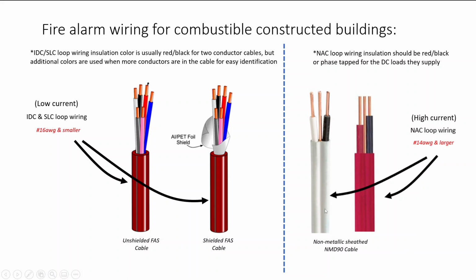And you could use just standard Loomex, or you could use this one. This is called HEDEX in the field, and the only difference is that it's meant for a 240 volt AC circuit, which means it has red and black. Now we're using it for a DC system, and so it helps that the coloring is correct, and it helps to distinguish it from some of the other normal building wiring that might be in the condominium. And so often contractors will elect to use this red jacketed HEDEX for the NAC system wiring of a fire alarm system.